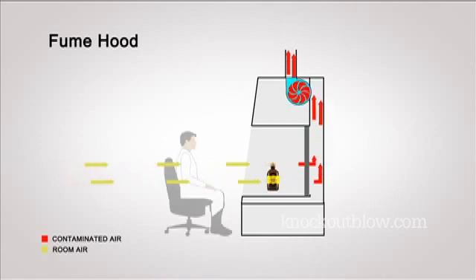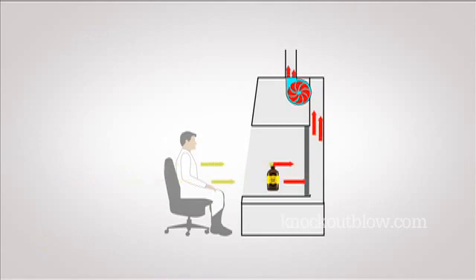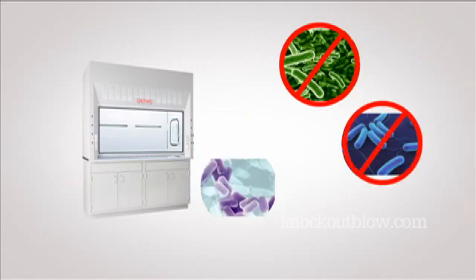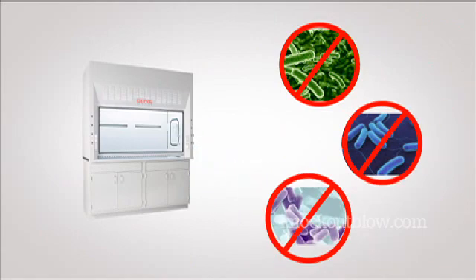When using a fume hood, a building engineer or technician should be consulted to ensure that the ventilation system of the existing building is adequate for the installation. Like the clean bench, the fume hood cannot be used for biological agents because there is no system to protect the user from biological hazards and it does not protect the product.